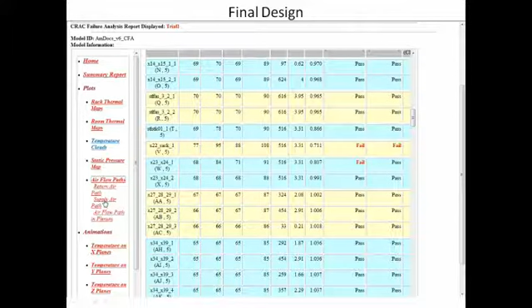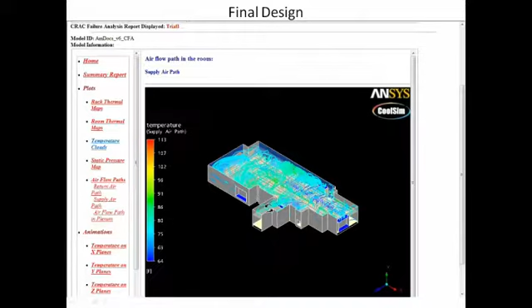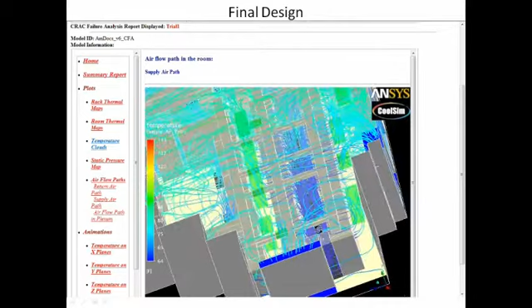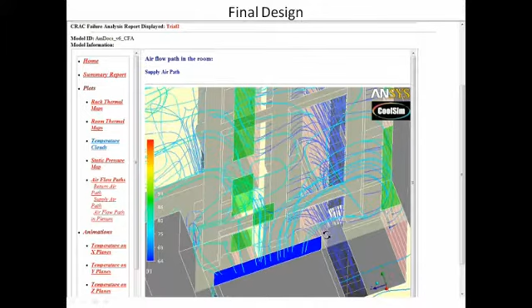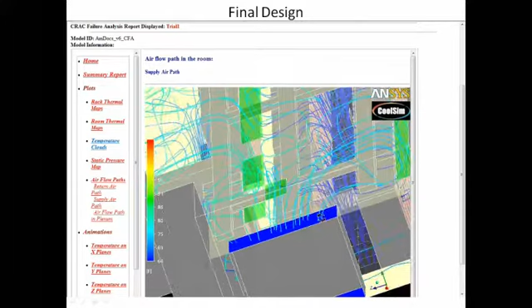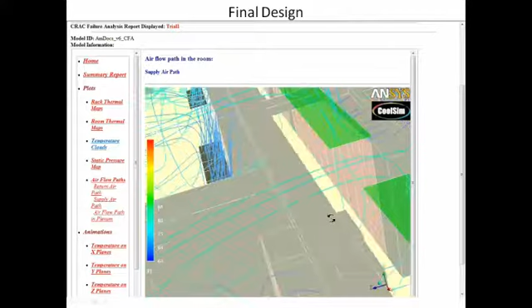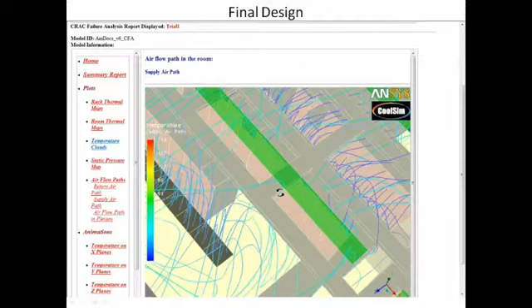One of the things I wanted to show here is if we take a look at the supply air, things are better than they were before because we've done some work on cold aisle containment. So the cold air can no longer leak out right here. You still see a little of it coming up through the grills in the ceiling, but it can no longer leak around these end caps. There are also some gaps on the sides right here, a little bit on the side too, but it's being better managed than it was before.